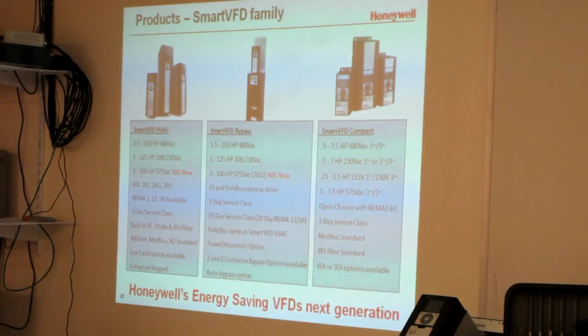That's the high frequency. On the low frequency, it puts out noise that you pick up with a scope, and it puts it off the input. So that's why you see the line reactors on the inputs, because the low frequency harmonics are what kill the motor and also screw up your computers and stuff in the building.